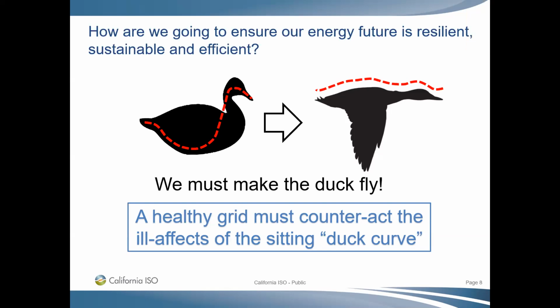Restrictions or limitations? Well, the restrictions, yes, there are, because as I mentioned, when we operate, you got a few things that you have to look at. So the system operators, they got to make sure that they operate or help support the interconnection frequency. We also have limits that are set by the North American Electric Reliability Council. And what that means is we have to operate between tight frequency bands. So your area controller and your frequency needs to fall within those curves. Also, we have a frequency response guideline that if something happens, we got 52 seconds where we need to react. And then also we have a contingency reserve standard where if you lose any element on the system, you're going to recover within 15 minutes.